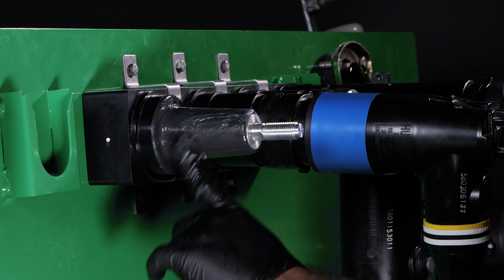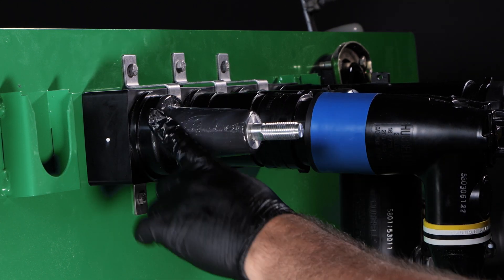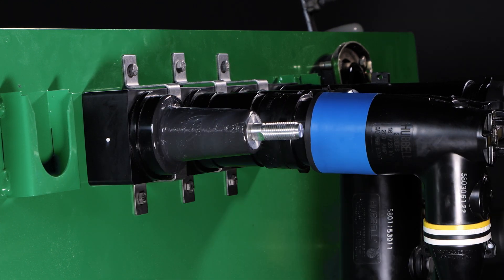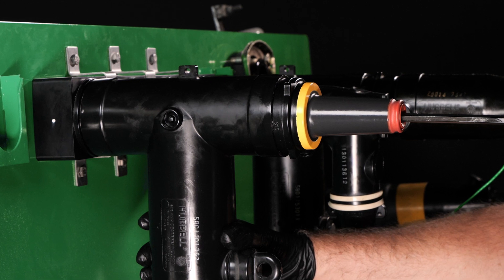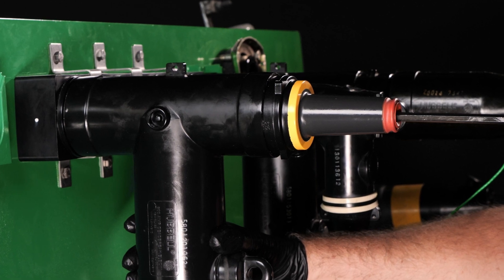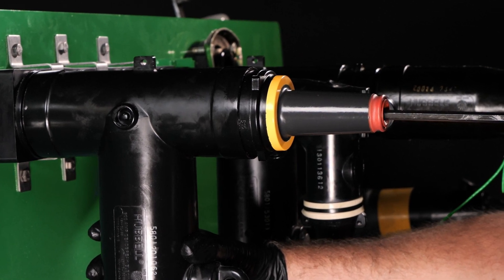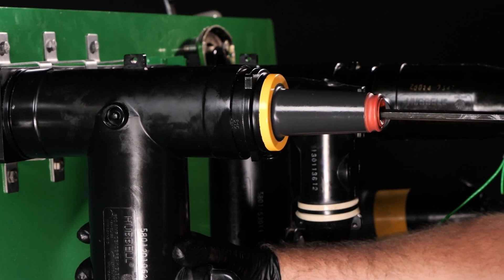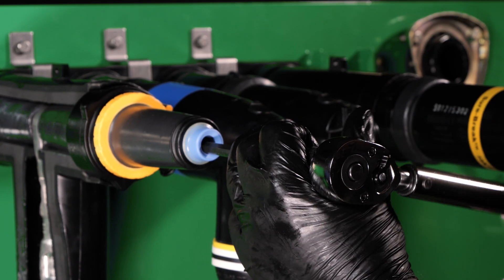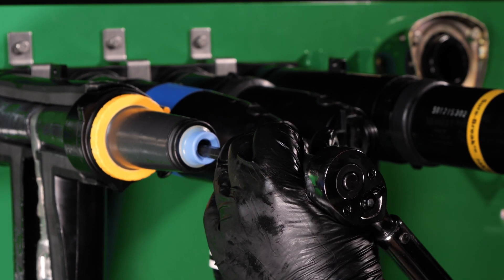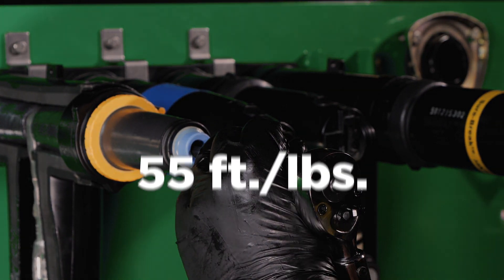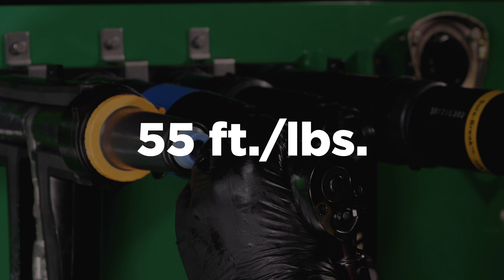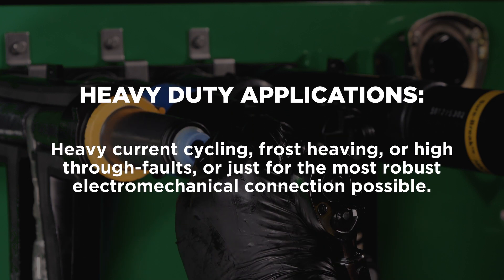Clean the apparatus bushing and add a thin, even layer of the supplied silicone grease. The SureTap should quickly tighten onto the stud using a five-sixteenths hex wrench inserted through the SureTap. The SureTap should be torqued to at least 20 foot-pounds. Hubbell recommends 55 foot-pounds for heavy-duty applications.